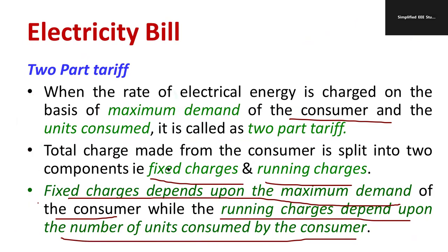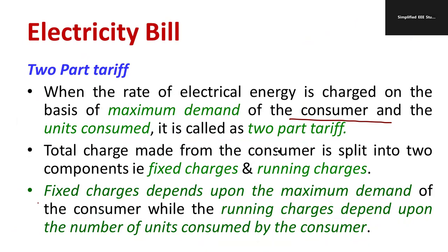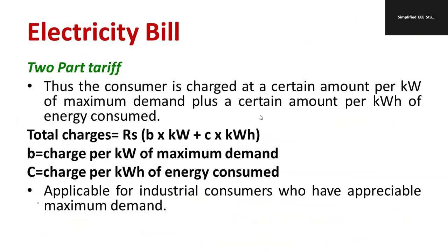That is what is called a two-part tariff. We should be familiar with the two components of two-part tariff. We can write a simple formula for computing the total electricity bill using two-part tariff. The total charge is given by: Rupees = B × KW + C × KWh. Here B × KW represents the charge per kilowatt of maximum demand, that is called the fixed charge.